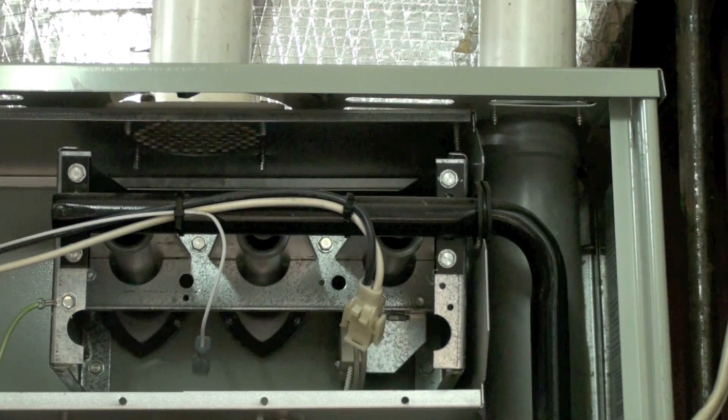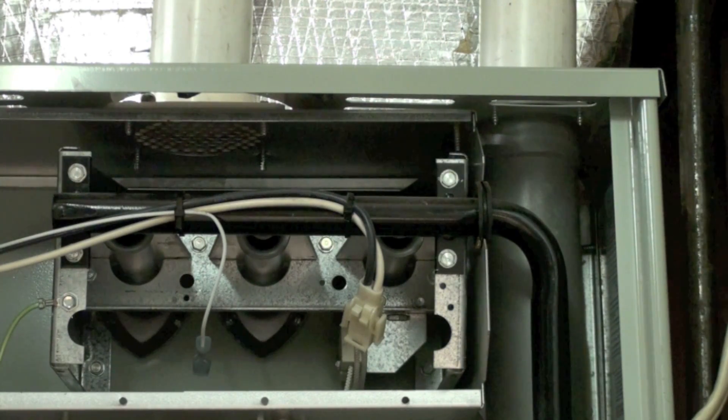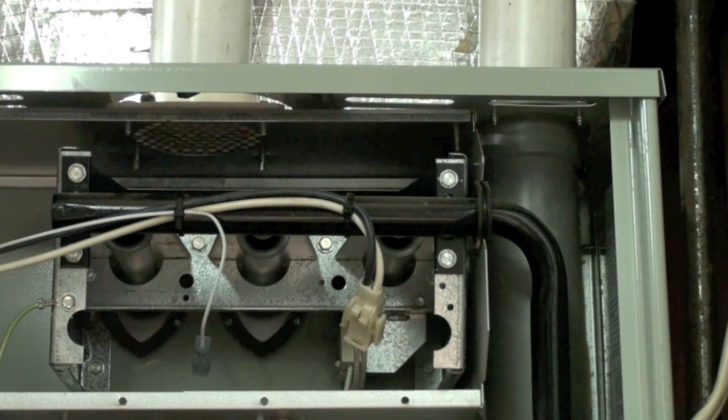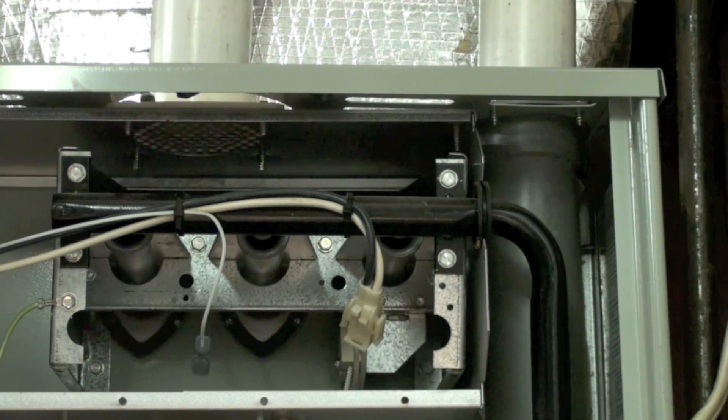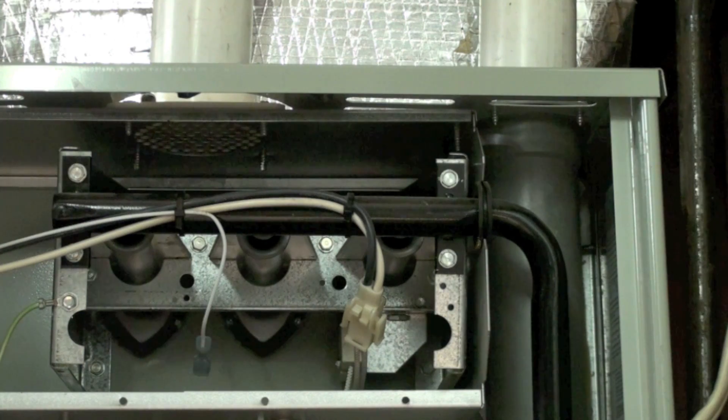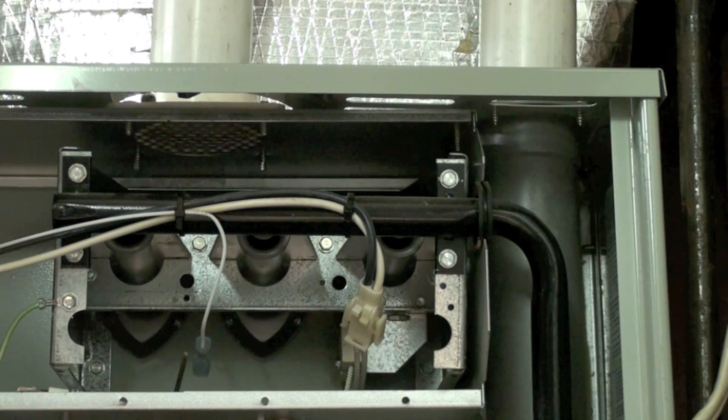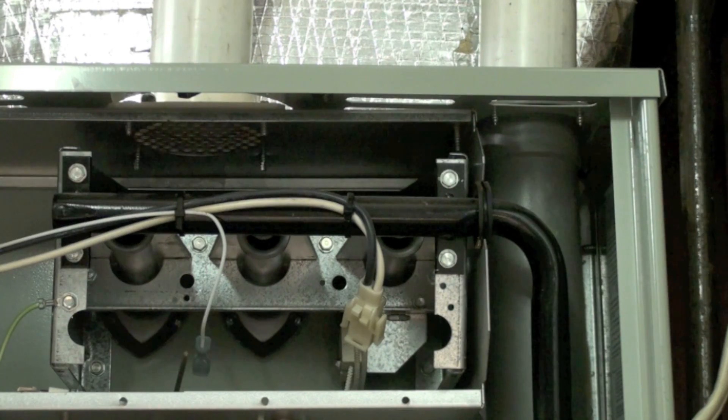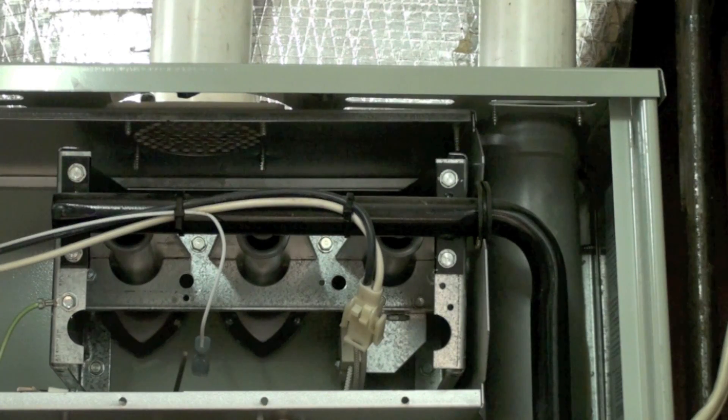The thing is very simple and there's a lot of talk about how they should be cleaned with this or cleaned with that. I'll tell you, I have been a heating and air conditioning instructor for a number of years, and when I sabotage furnaces I do everything I can to get that flame rod not to work. I can't get them to not work. I put duct tape on them, soak them in chlorine and so on, and I can't get them to fail. So I don't think a little bit of sandpaper residue is going to make much difference.